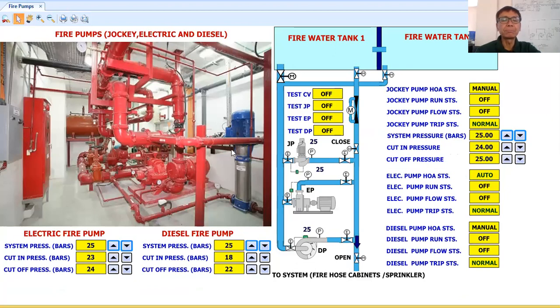So what are the pumps in a fire pump room? Basically, there will be three pumps, okay? So the first pump will be the jockey pump. Okay, so this is my jockey pump. Then I have my electric fire pump here. Then at the last part is my diesel fire pump, meaning there will be a diesel engine there to drive the pump, okay? Now, as you can see there, I have my day tank for my diesel fire pump. Then here are the fire pump control panels, okay?